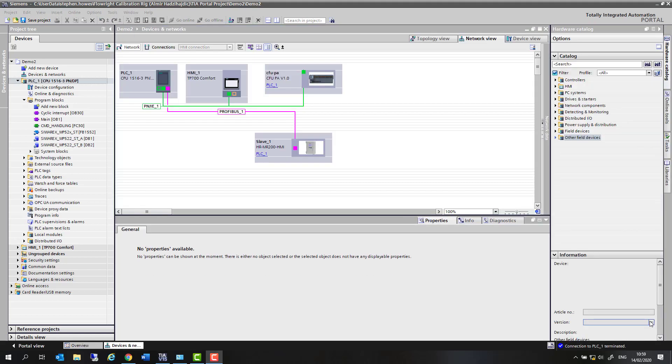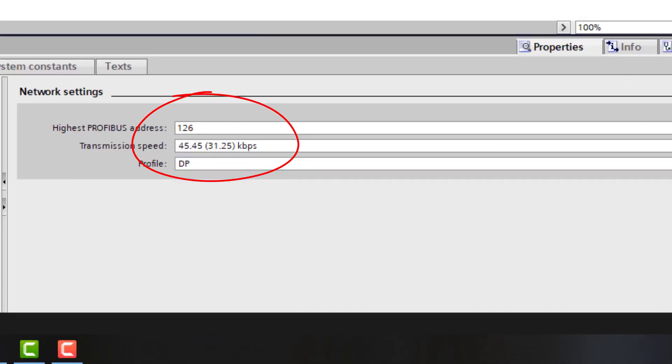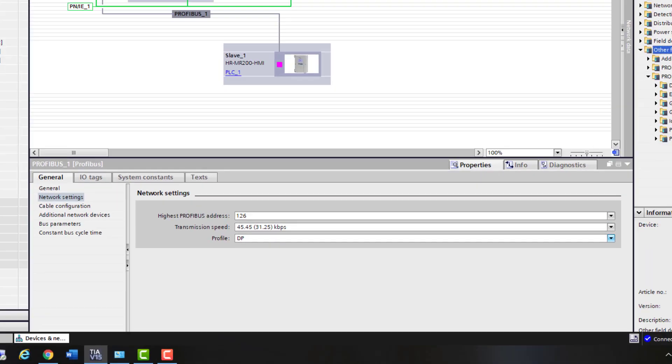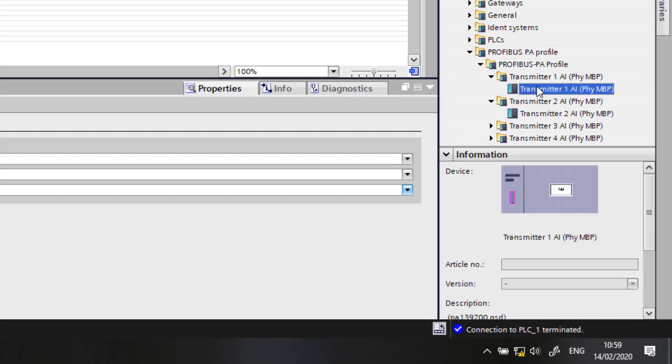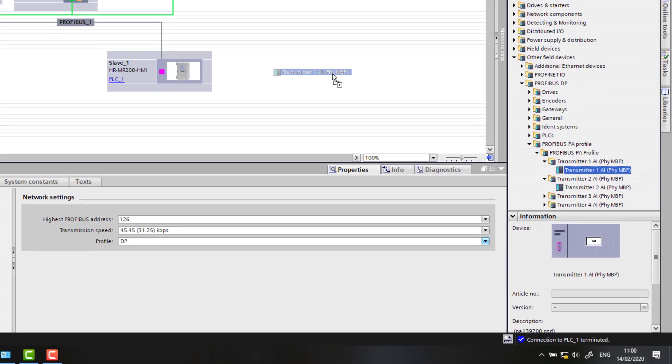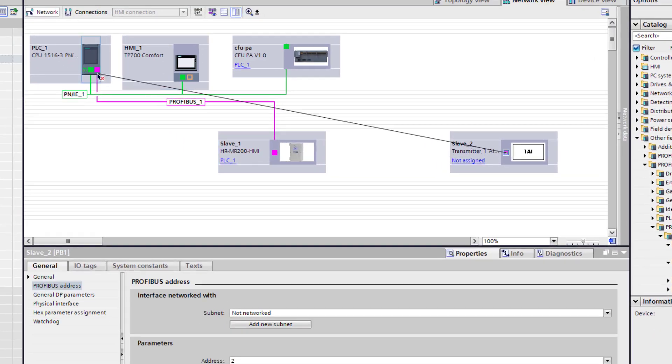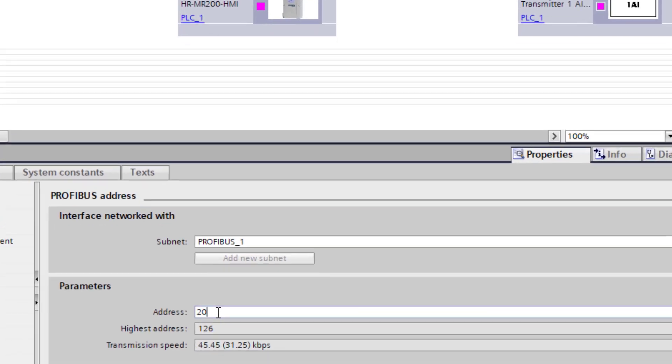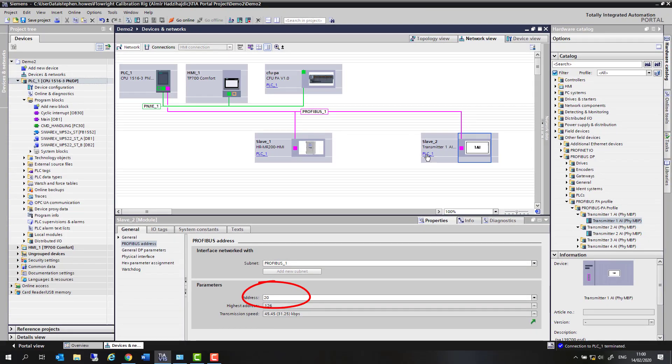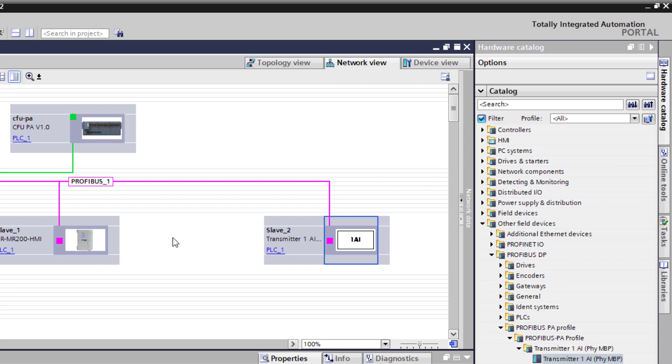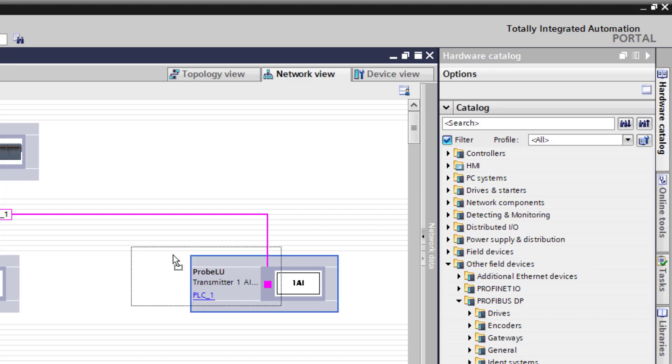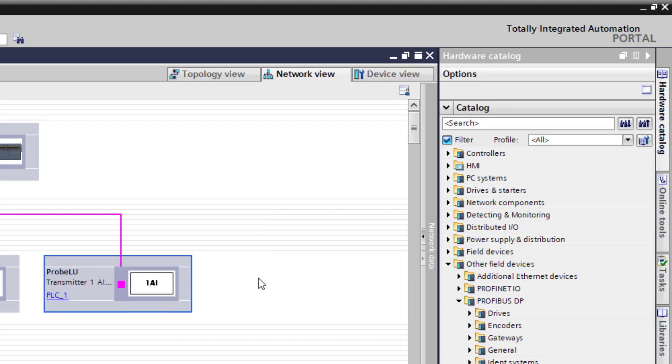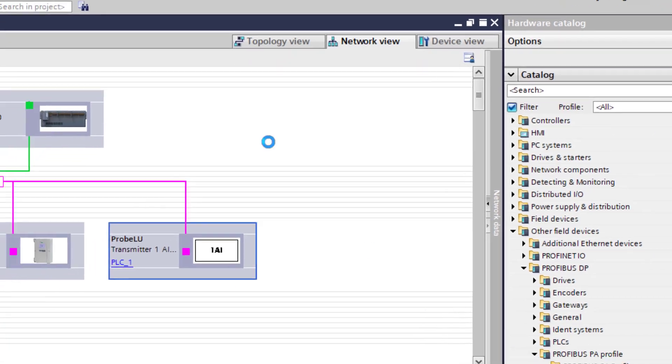So now we've installed the GSDs, we've slowed the bus speed down to the Profibus PA speed. We have to add the device, and it's under field devices, the transmitter with one output. Link that to the master, make sure the address is set right for the device, and if you want to rename it. So this will be your site tag, but that's what will also appear on the HMI for you if you've got the advanced license. The special block you can bring in and also on the display for the 1500. So we'll download that.